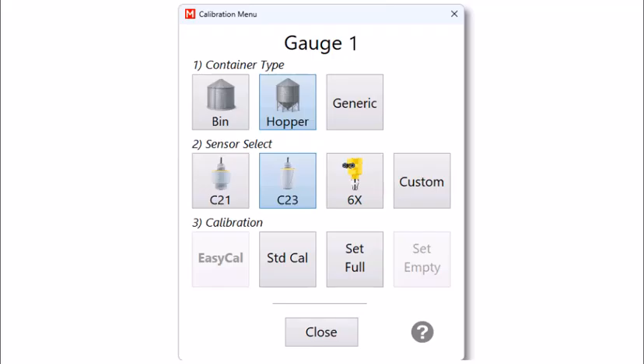In the Calibration menu, we have a number of options for defining our bin setup and choosing how to calibrate it. We will talk through each type of bin and the available calibration options. But first, let's make a quick note of the sensor selection options. The most common sensor selection will be the C21, followed by C23. You may also select the 6X if your system is using that sensor model. There is also an option for a custom sensor. If you ordered a custom sensor solution from MTEC, please contact us for further instructions on performing a calibration with that sensor. Now we will move on to the container types. The first container is the standard bin with a flat base.